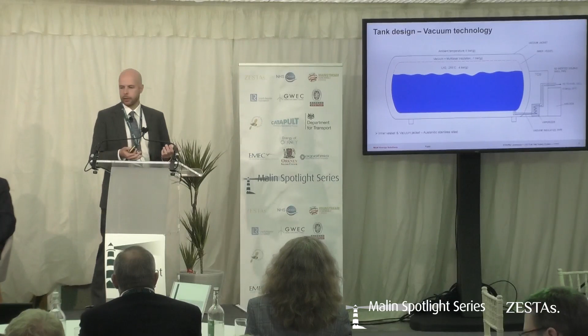In order to never have any leak and exposure of gaseous hydrogen to the environment, because this is an explosive and dangerous gas if you don't treat it right, all the piping is either vacuum insulated or pressurized with nitrogen. If you have a vacuum insulated double wall pipe, we have an inner pipe that transfers the media. If this pipe were to leak, the leakage will not go into the air, it will go into the second pipe, which is covering outside.